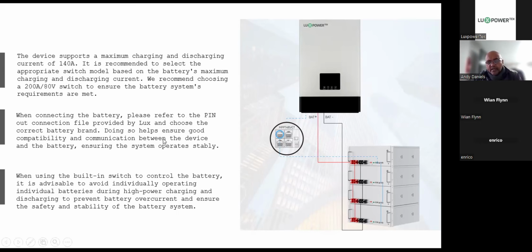One thing I want to point out to you guys is that if you look here on the screen of the SNA, the information that is shown here, especially on the battery side, if you're using battery communication, as well as on the monitoring side, that information is information that we get via the communication cable from the battery BMS, okay? It's not information that the inverter is calculating and putting up there. Unless, of course, it's a lead acid setup, then we do a calculation.